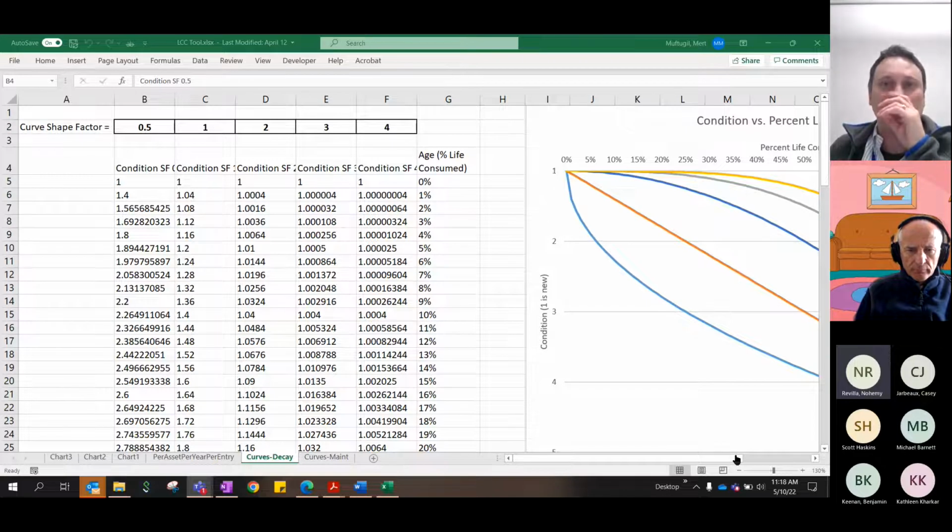So what I mean by that is, if we go and get a condition rating of 2 today, then 4 years later we do it and it's 2.5. I'll enter those points, and then if I need to fill in the gaps, I'll just apply either a linear or some sort of a curve, but I'll fill in the blanks.